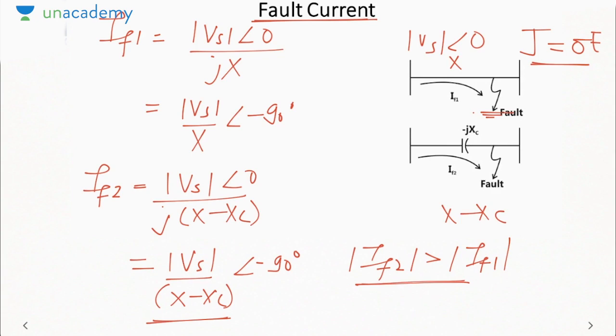That is why the rating of the circuit breaker will be higher and the cost will also increase. So an increase in fault current leads to more cost of the protection system as compared to a lower value of fault current. So remember, fault current determines the rating of the circuit breaker. An increase in fault current increases the rating of the circuit breaker and hence increases the cost of the circuit breaker.